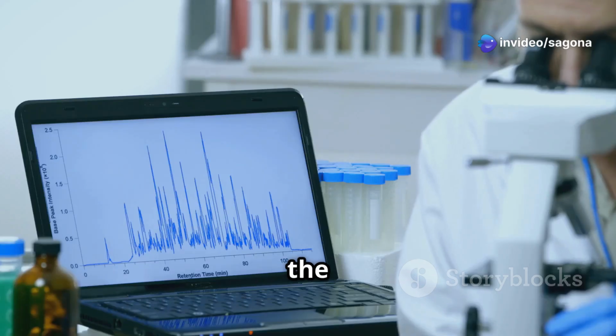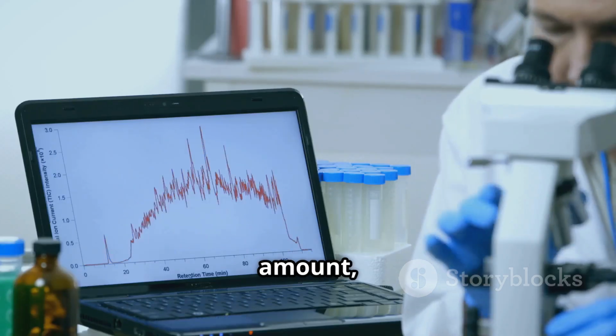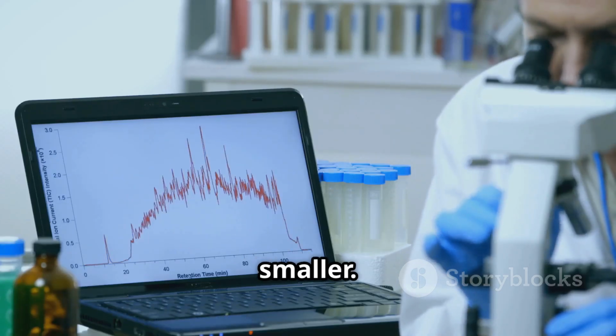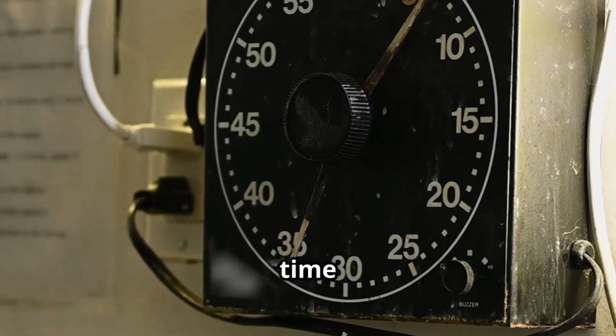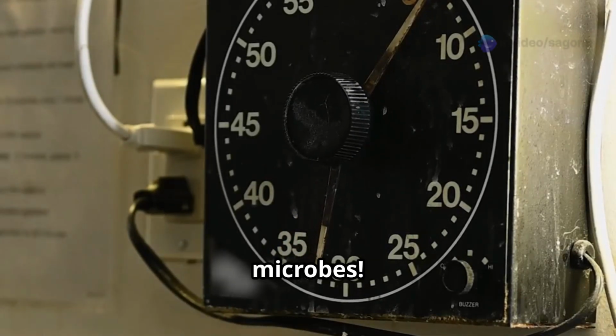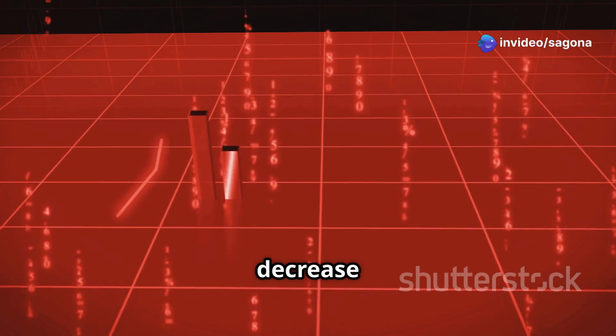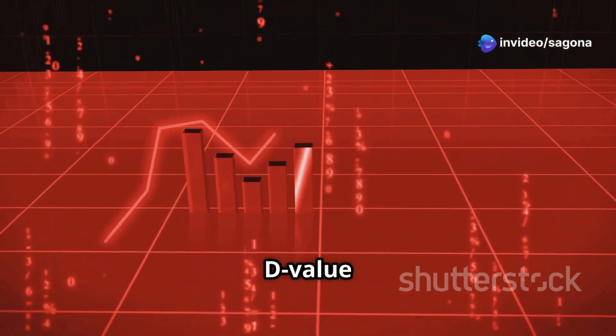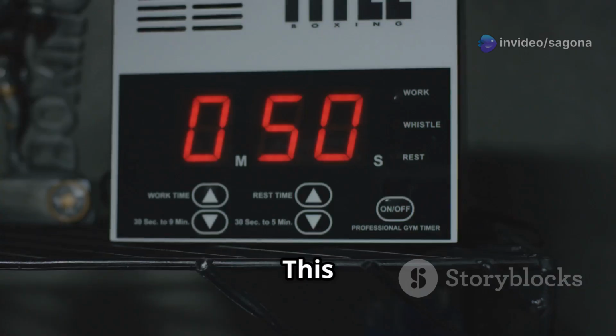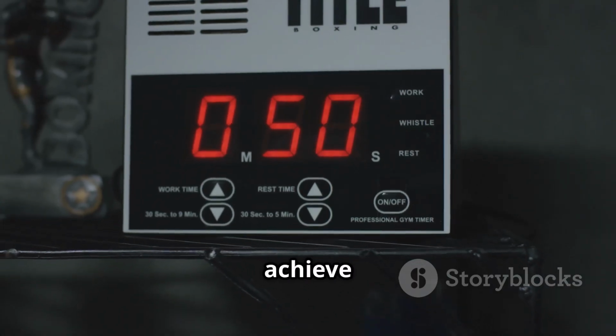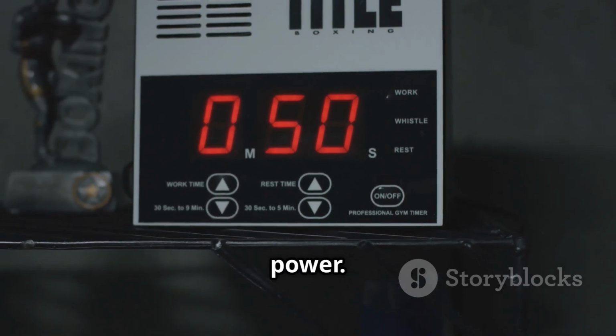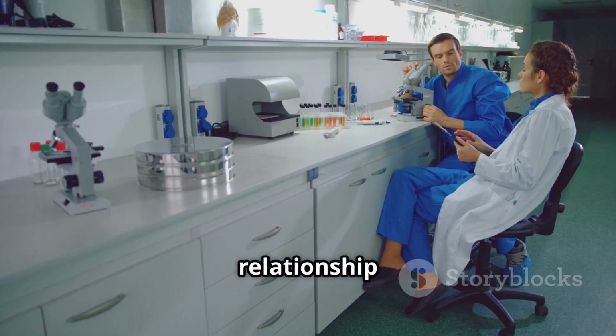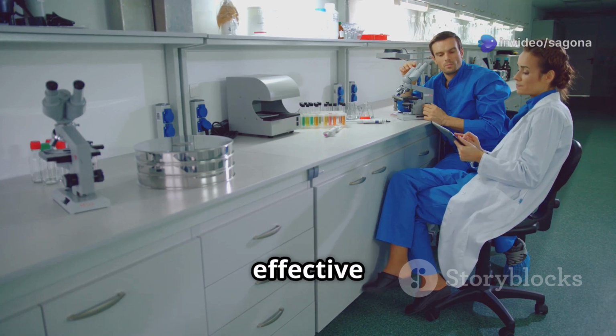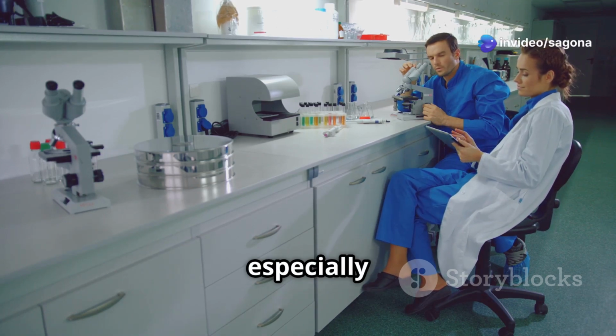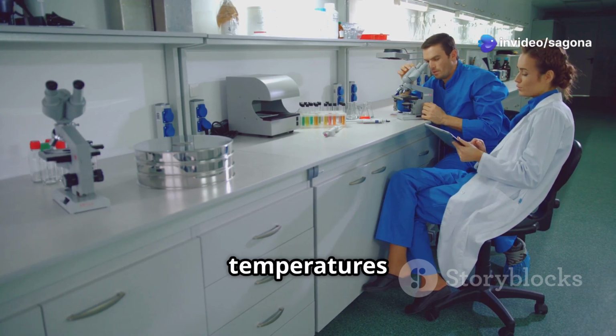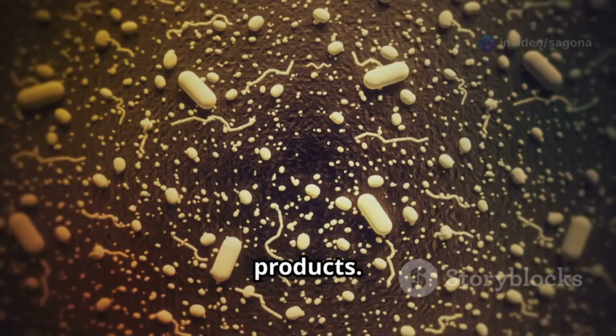If we increase the temperature by the Z value amount, the D value becomes 10 times smaller. That means it takes 10 times less time to kill 90% of the microbes. Wow. Conversely, if we decrease the temperature by the Z value amount, the D value becomes 10 times bigger. This means it would take 10 times longer to achieve the same level of germ-killing power. Understanding this relationship is super important for designing effective sterilization processes, especially if you can't use very high temperatures for some delicate products.